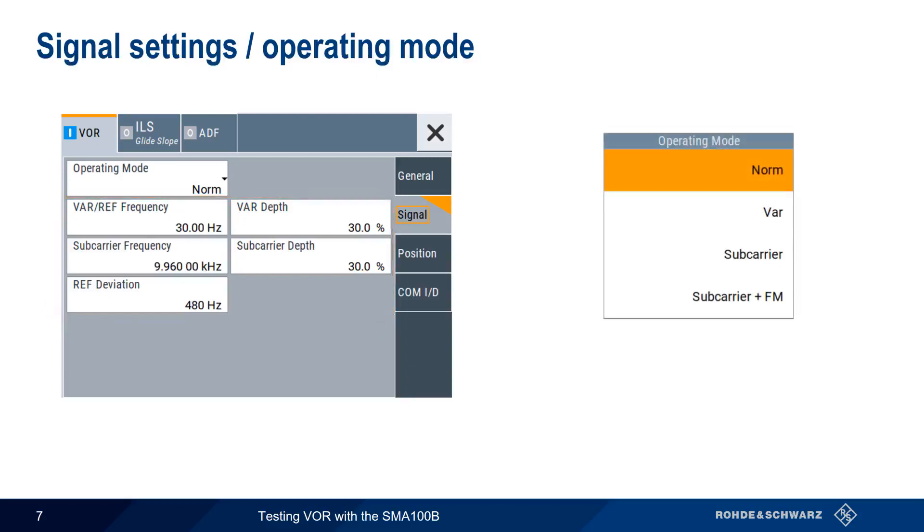The four different operating modes control which of the VOR signal components are present and or modulated. NORM generates the standard VOR signal with the optional COMID, whereas the other three options selectively enable the variable and reference signals with or without modulation. Again, to generate a standard VOR signal, the default values for operating mode and signal modulation should be used.